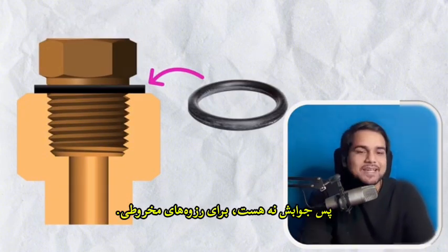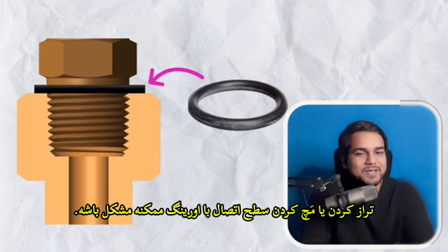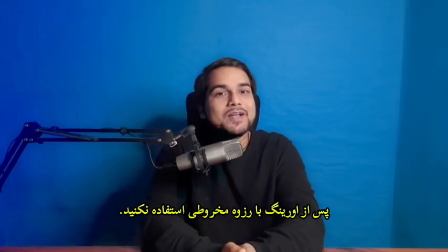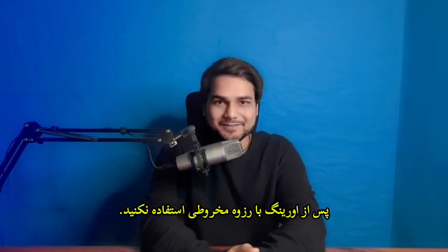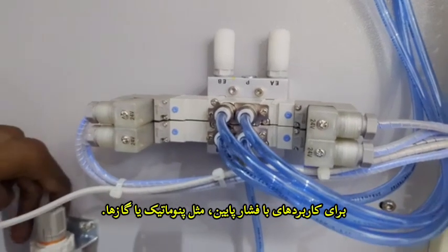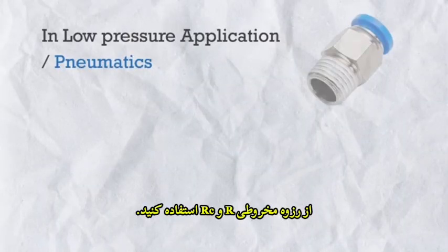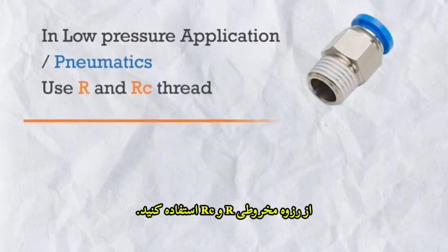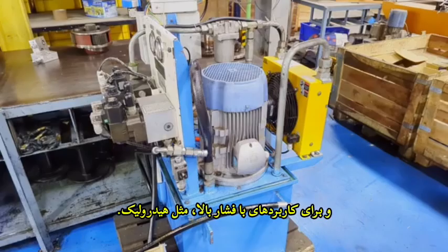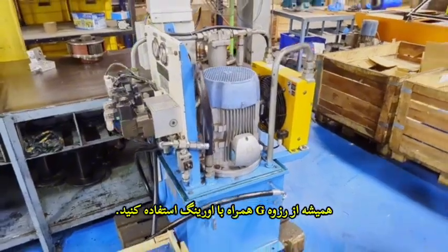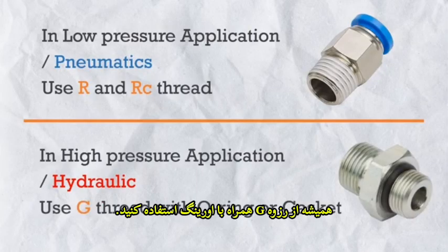So no. In taper threads, connection face matching can be difficult. So always avoid O-rings with taper thread. So in summary, for low pressure applications like pneumatics or gases, use taper thread R and RC thread. And for high pressure applications like hydraulics, always use G thread with O-rings.